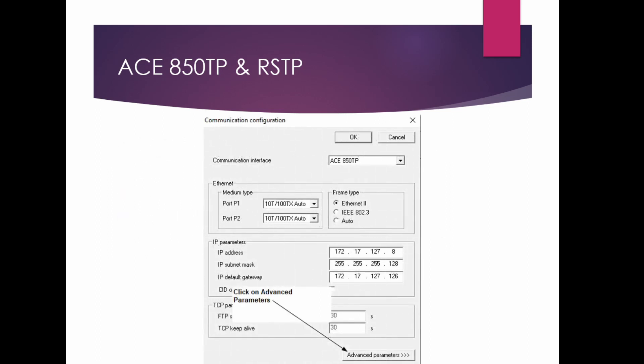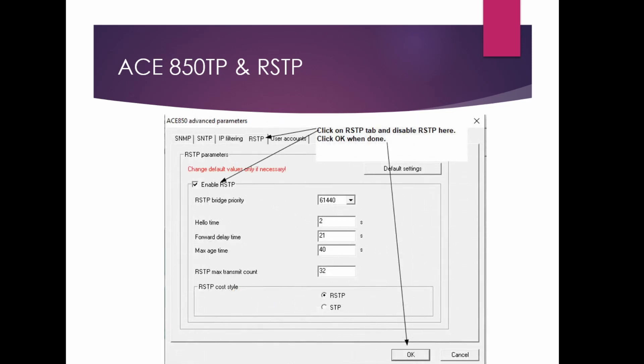If that's the case, you may have to disable the RSTP function. To do that, from the setup screen click on Advanced Parameters. When it opens, click on the RSTP tab — it's enabled by default. Uncheck it and click OK to disable RSTP, so it won't appear as an unmanaged switch to your IT department.